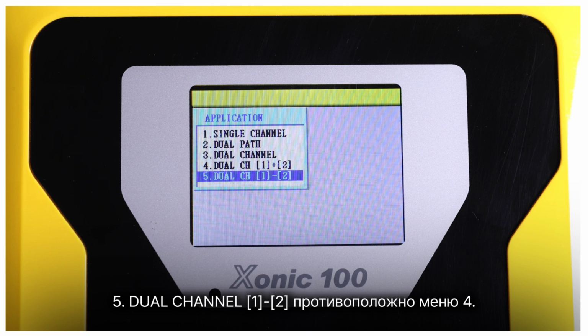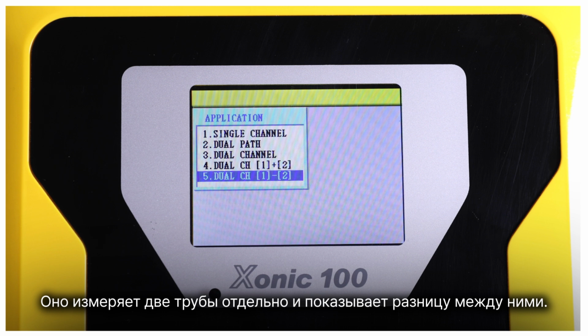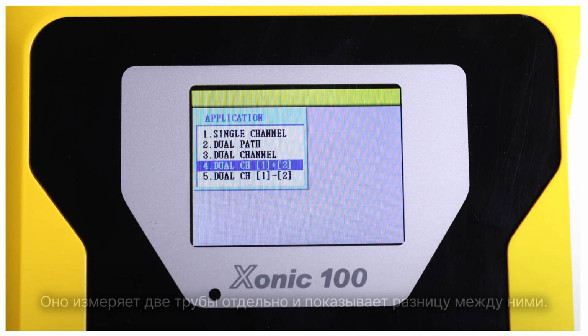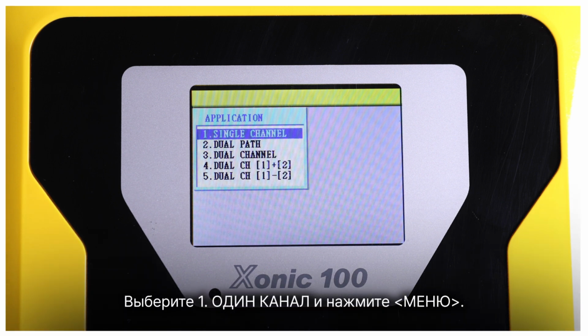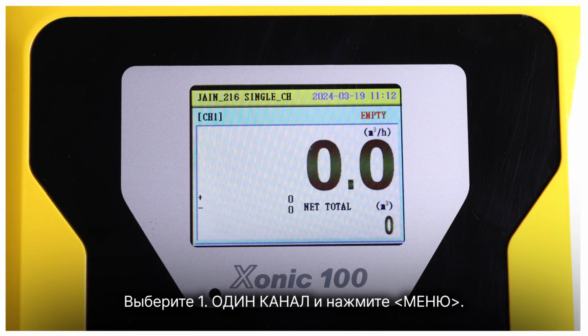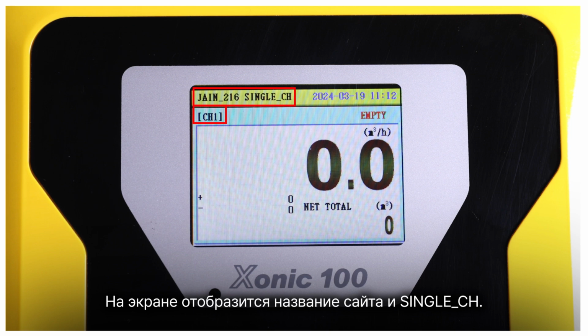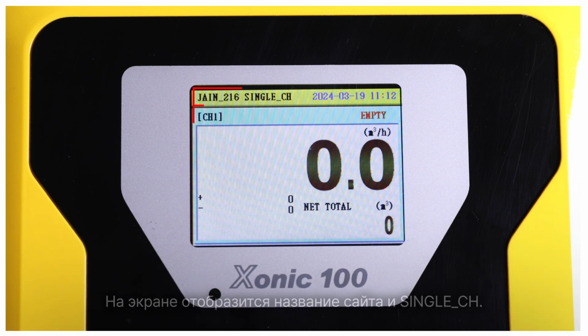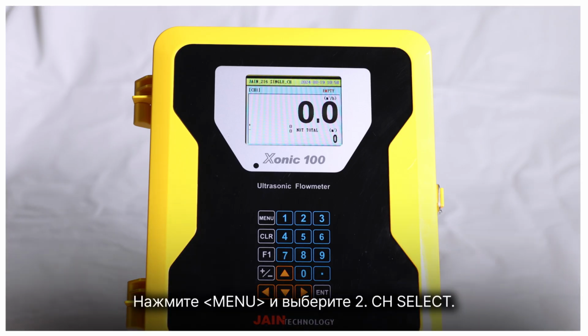5. Dual channel 1-2 is the opposite of menu 4. It measures two pipes separately and shows the difference between the two. Select 1 single channel and press Menu. You'll see the site name and single channel displayed on the screen. Press Menu and select 2 Channel Select.